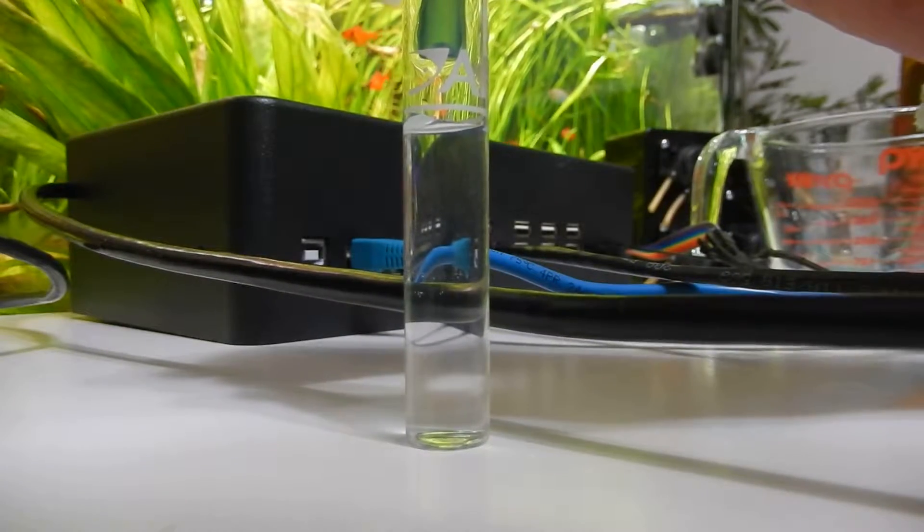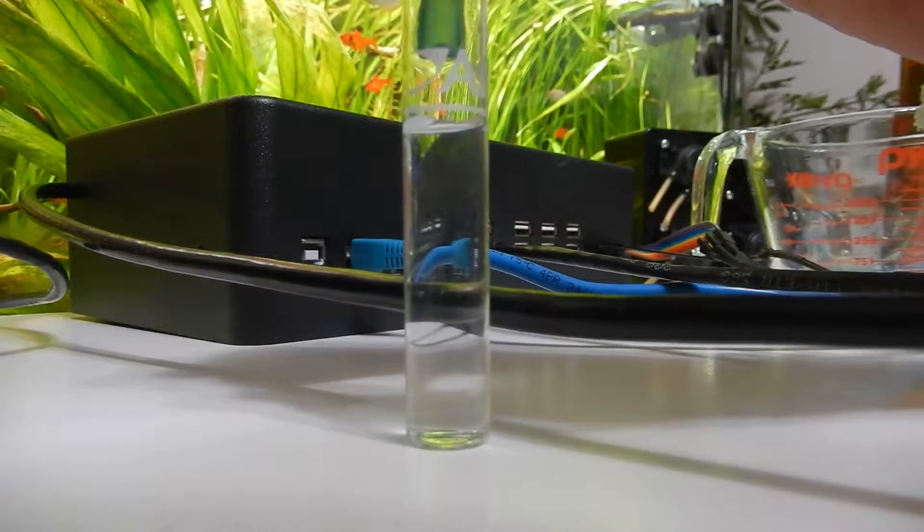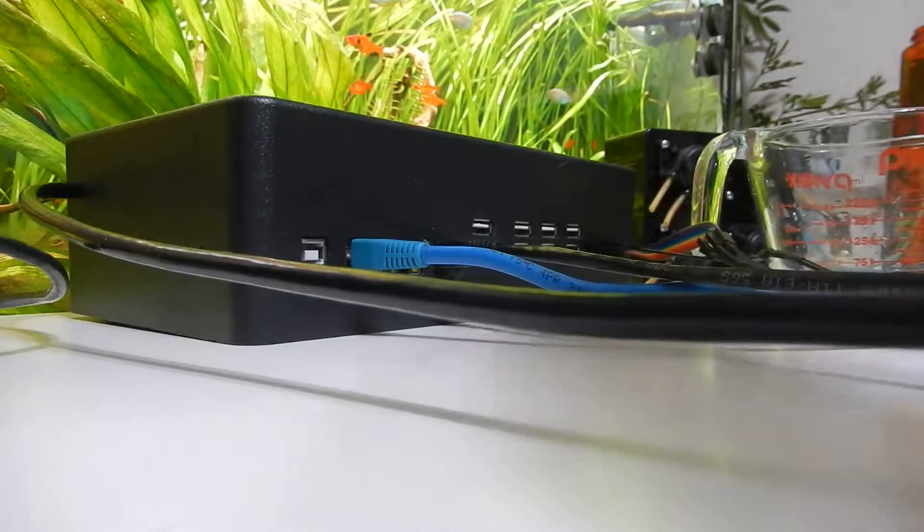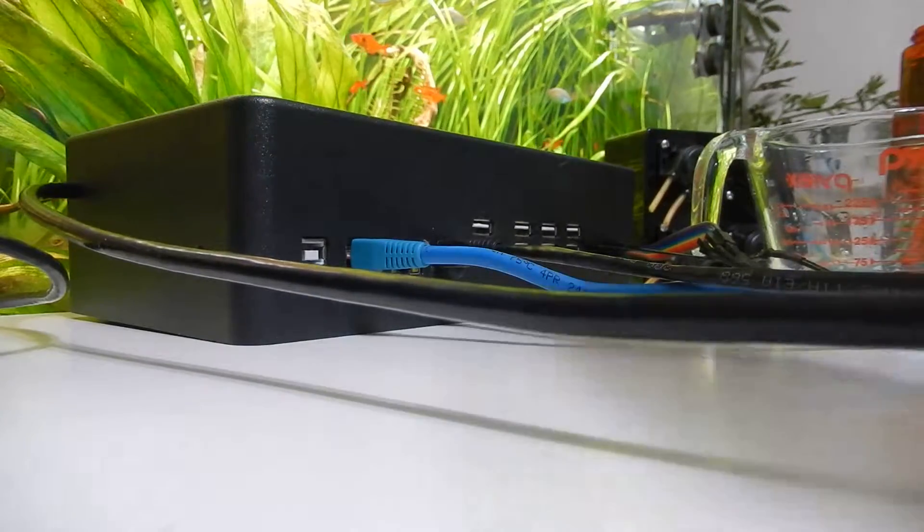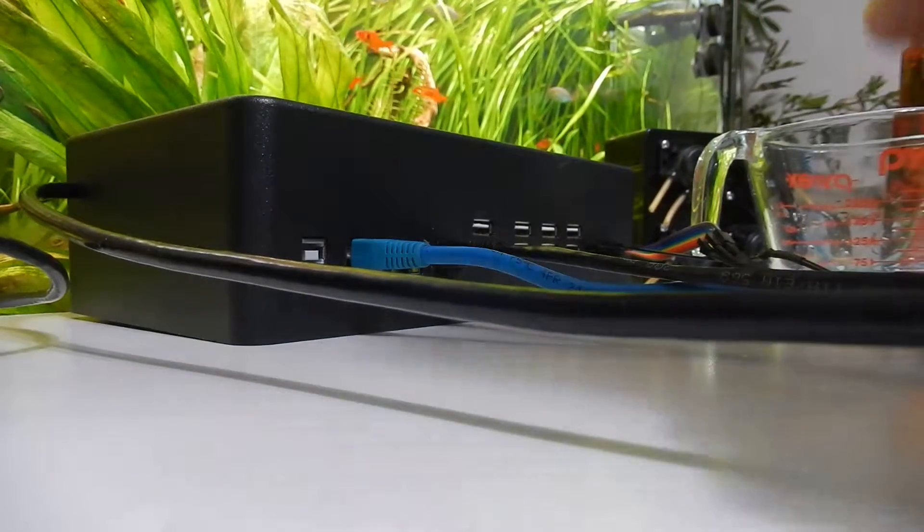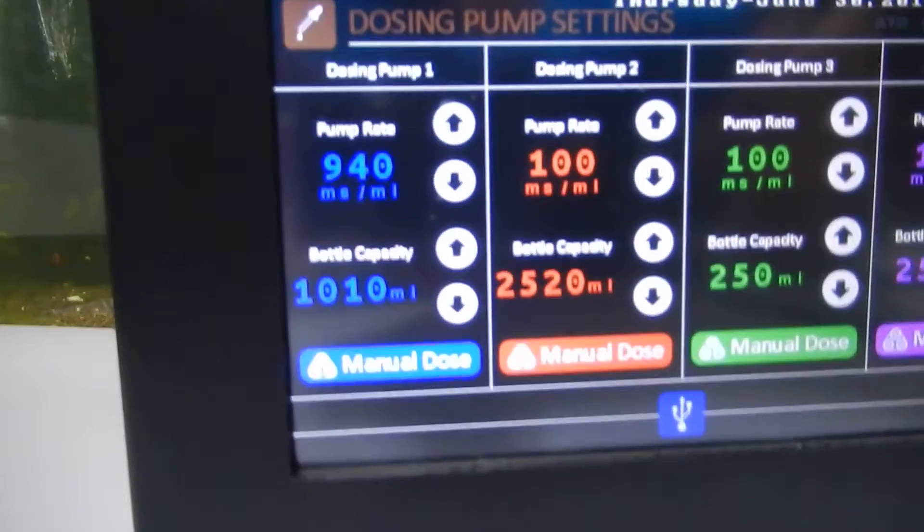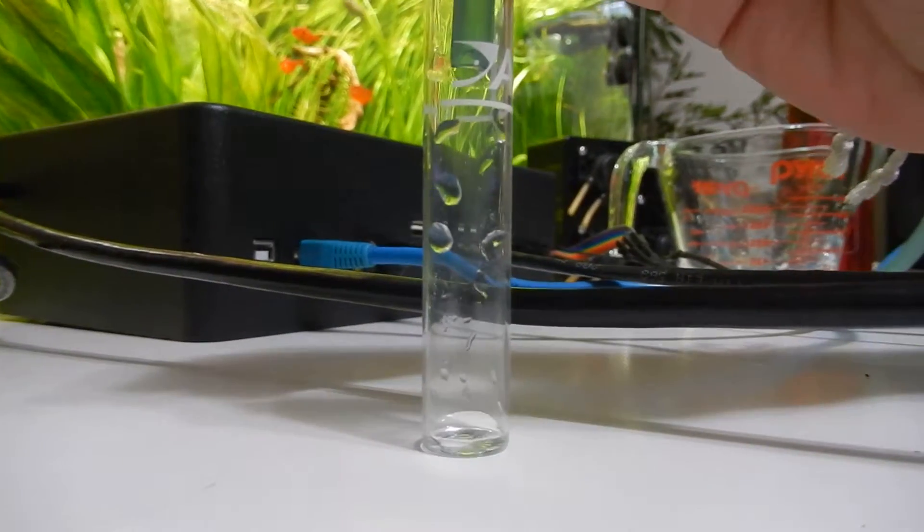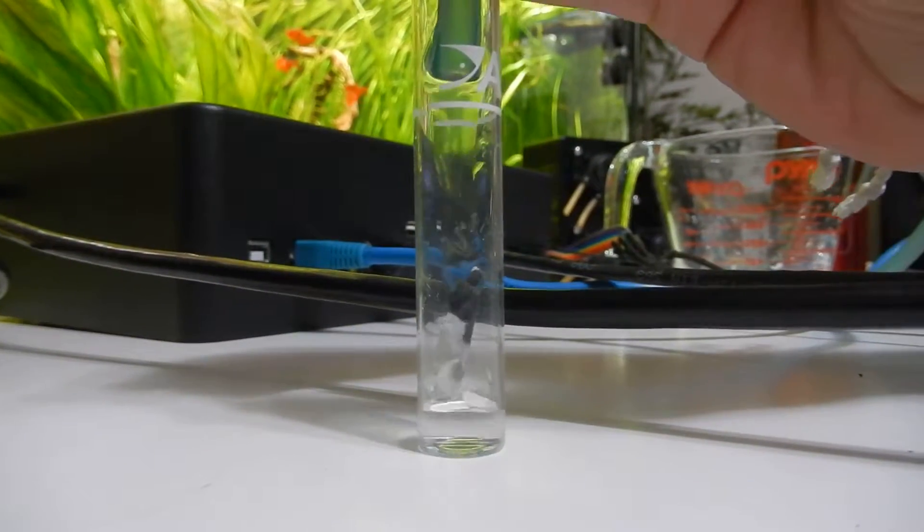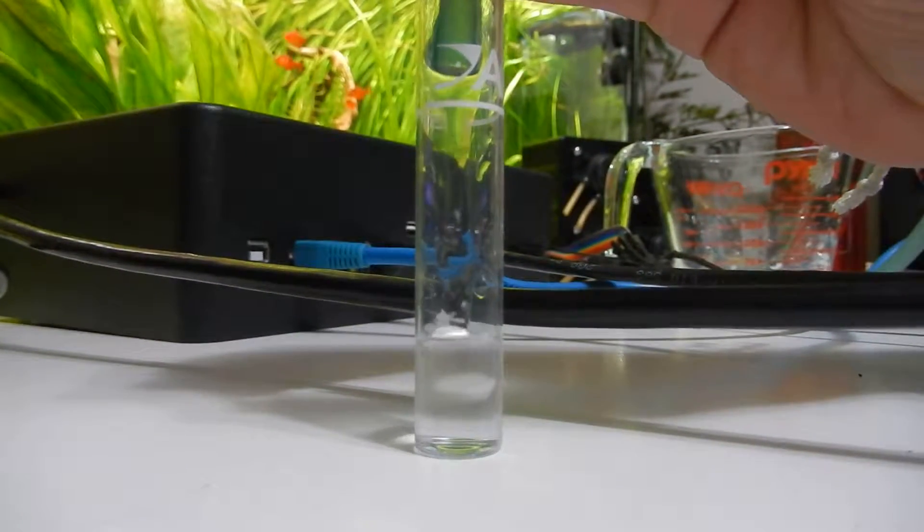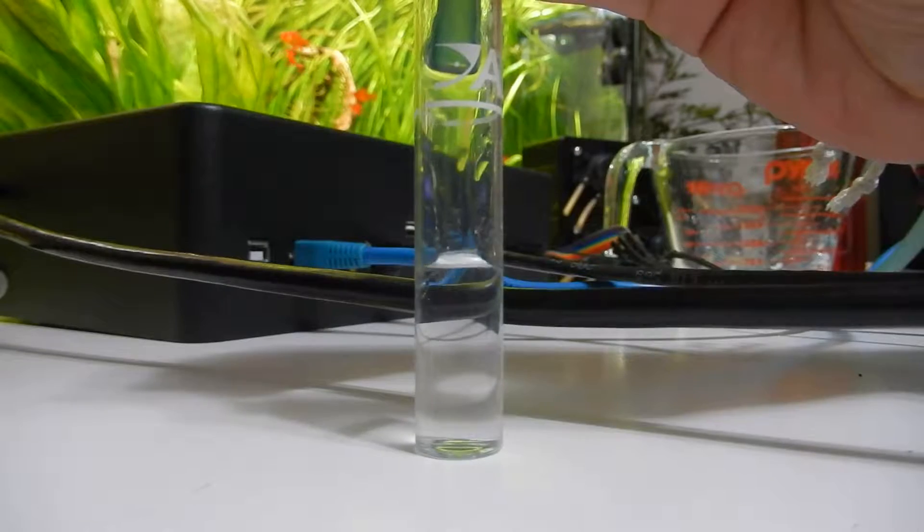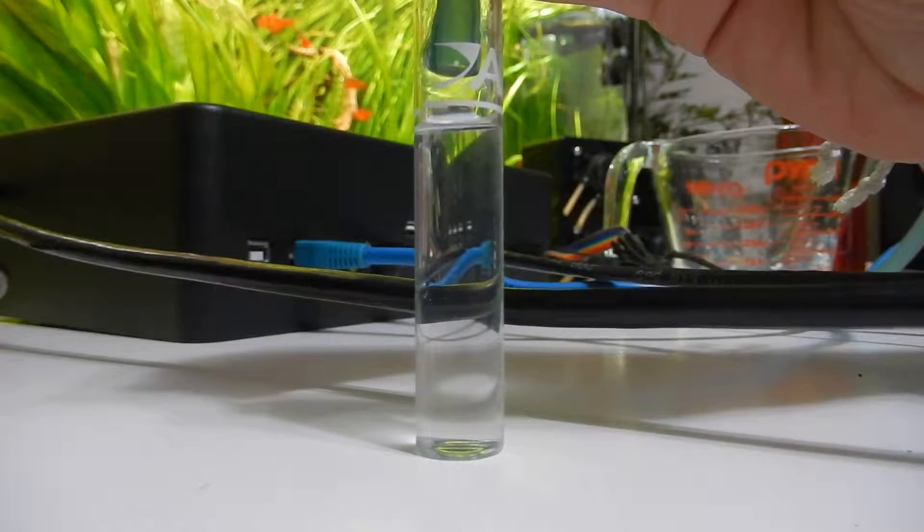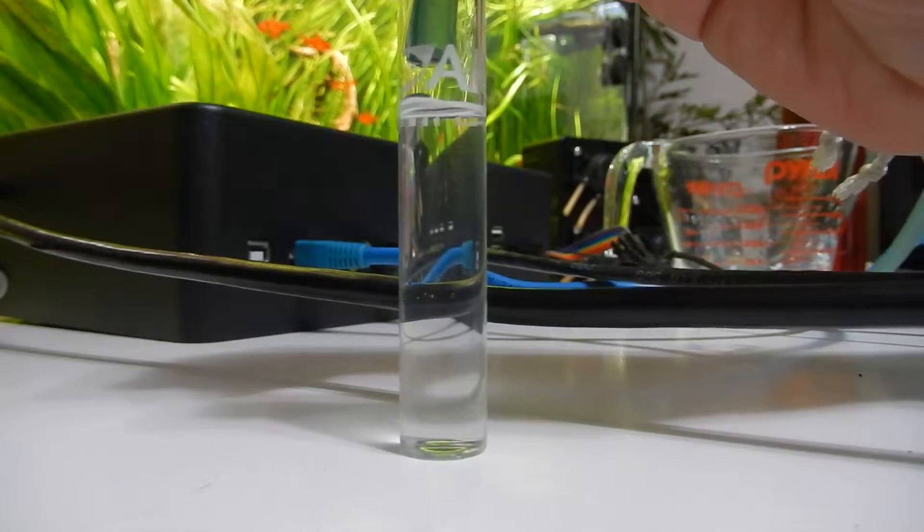So we'll up it to 940. Empty our tube. I'll just show you we've got 940 set there now. We'll push manual dose. And there it is. Perfect.